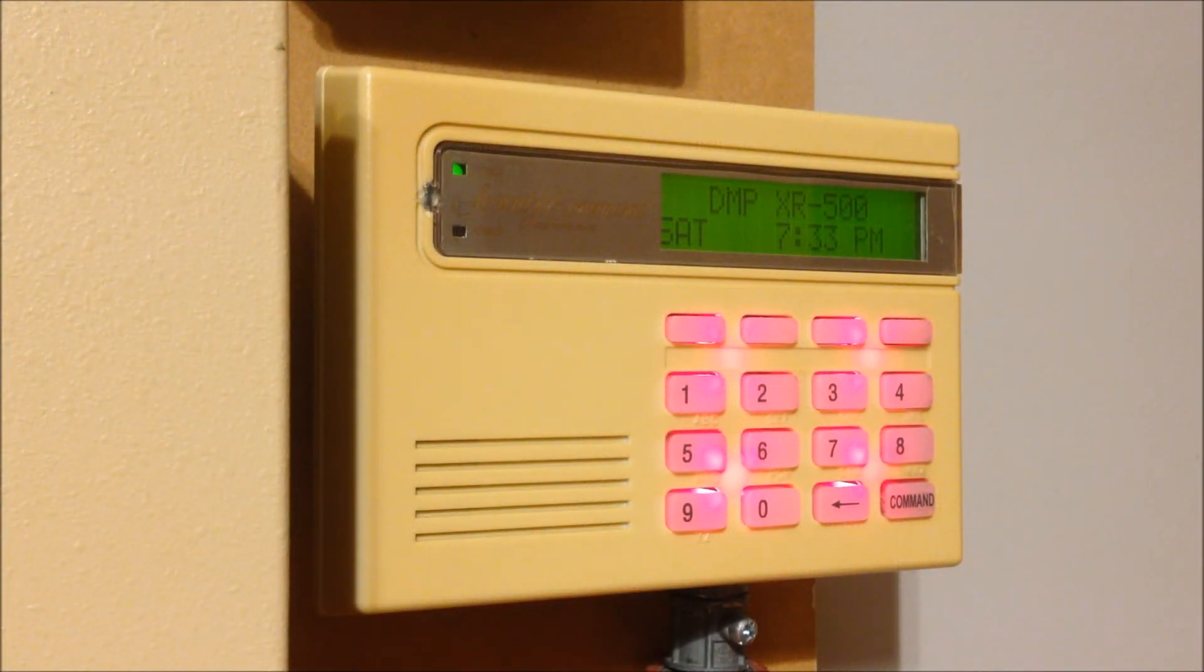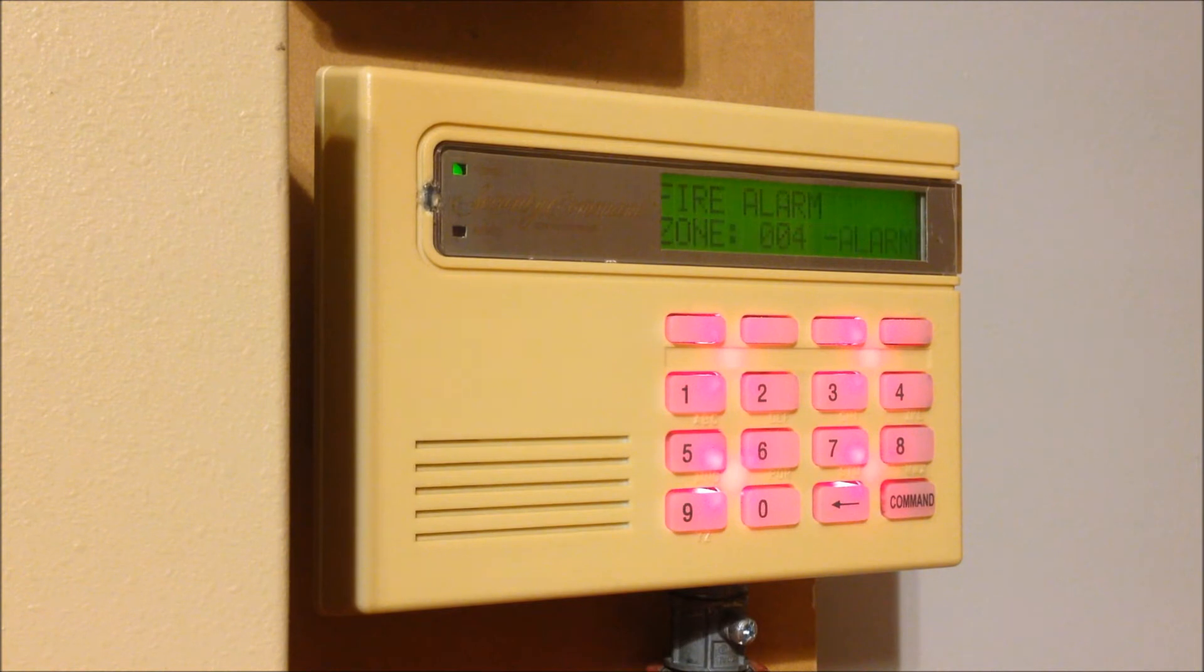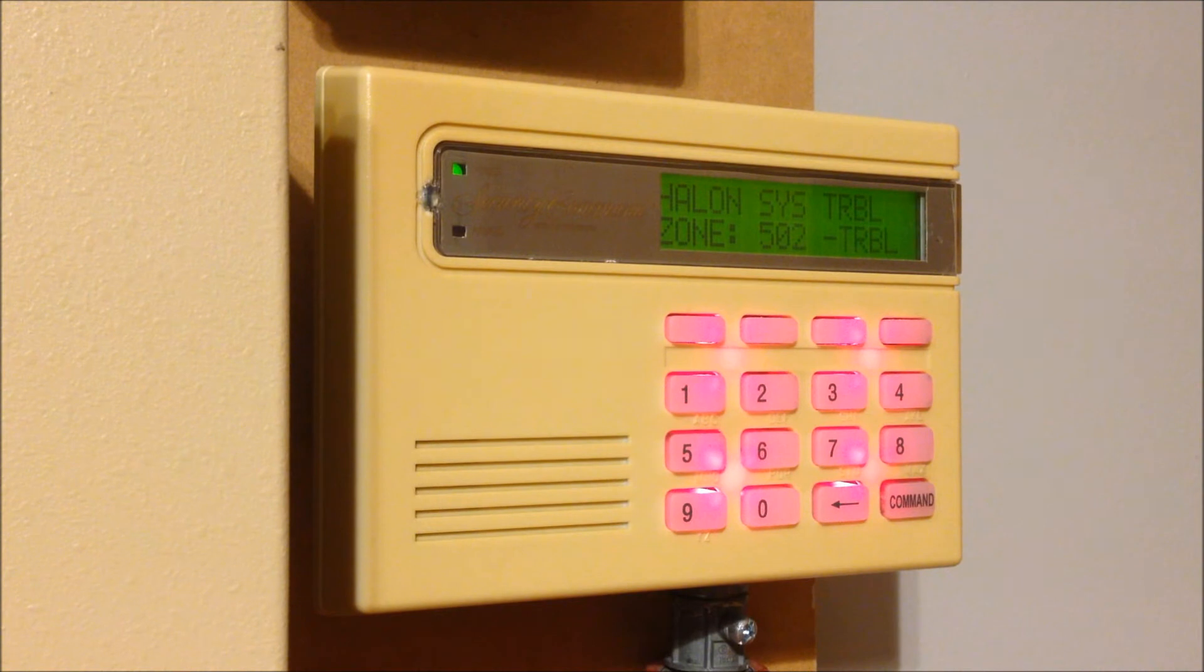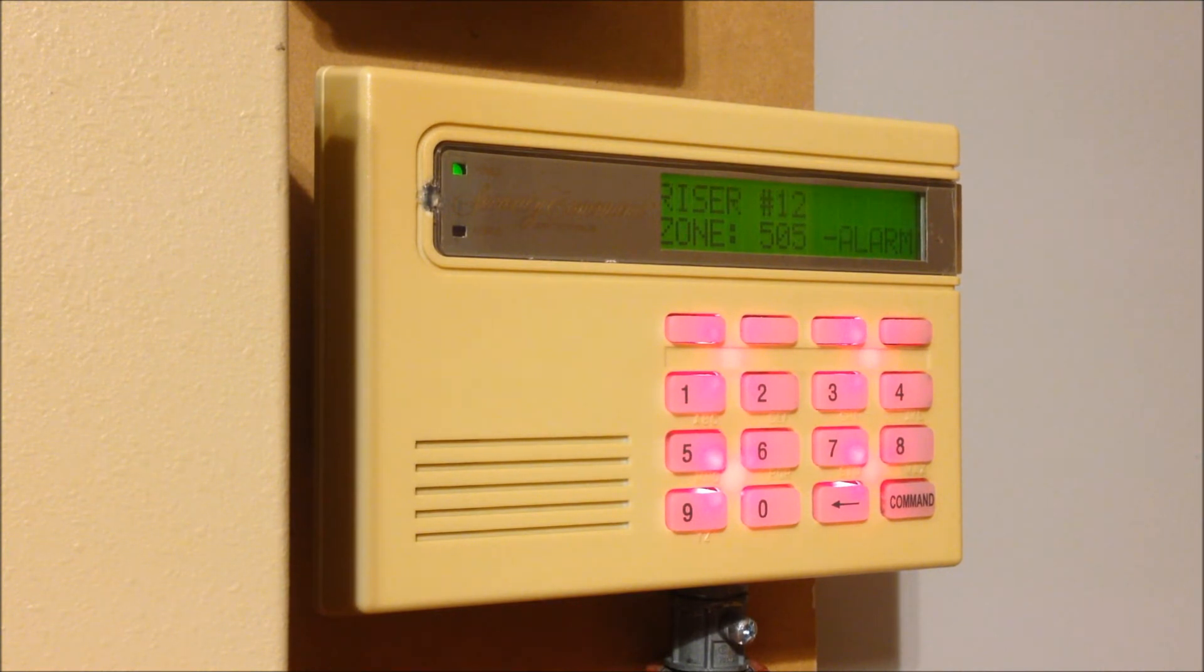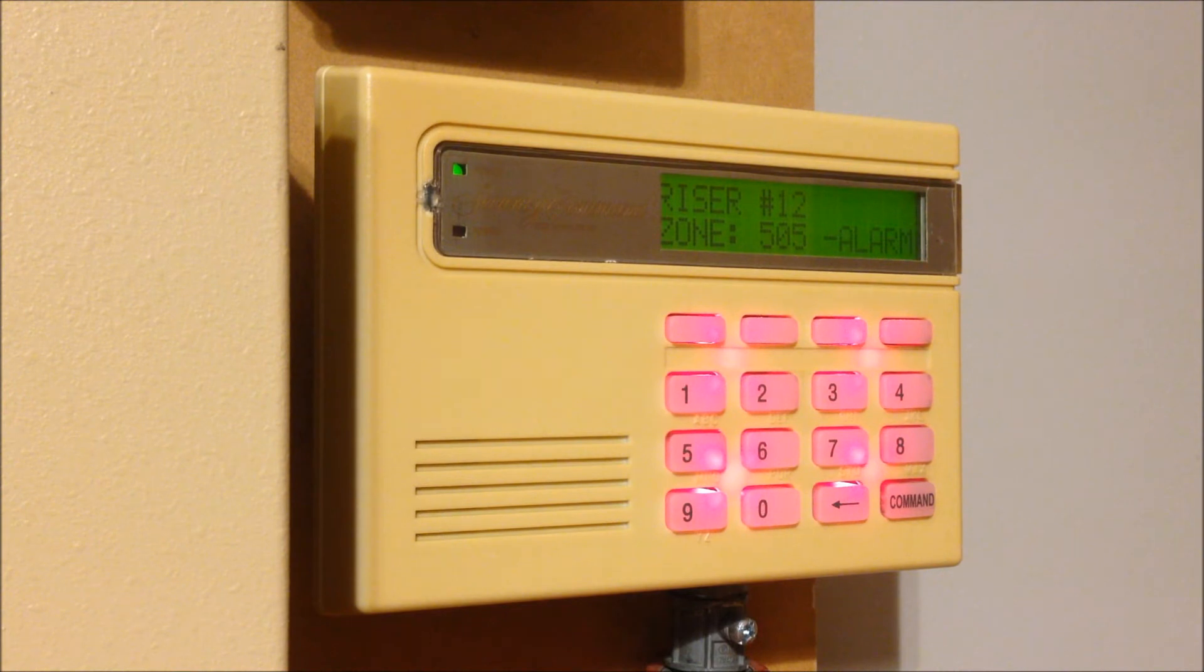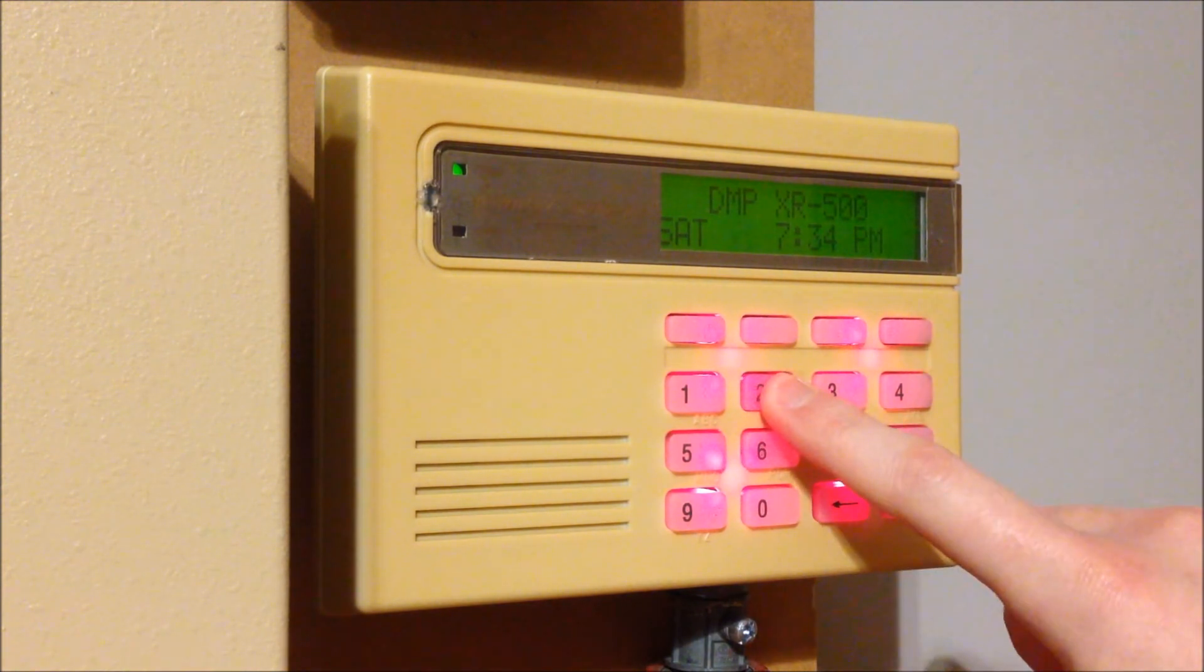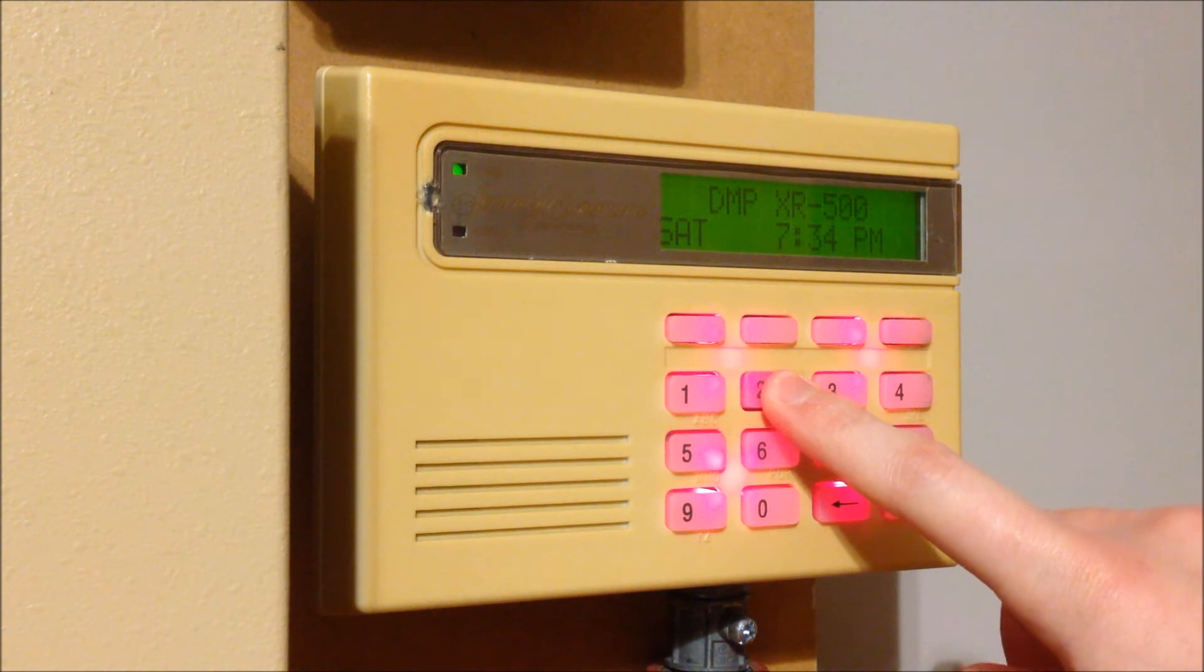And now I'm going to go ahead and reset the DMP system. I've been silencing this in the background, but you'll be able to see all of our alarms here. We have the fire alarm. There's a Halon system trouble because I don't have it powered up for this test. And then you see the fire riser alarm point on the keypad. So we can go ahead and reset this.